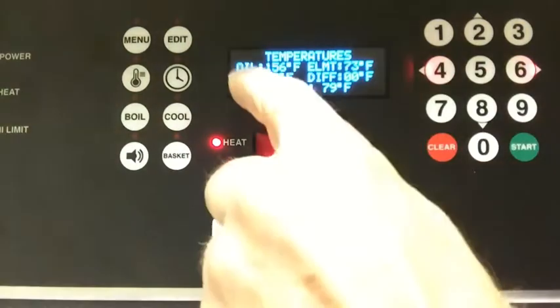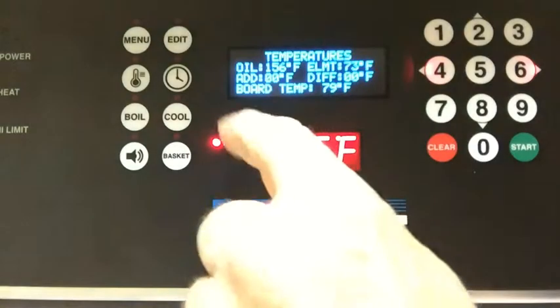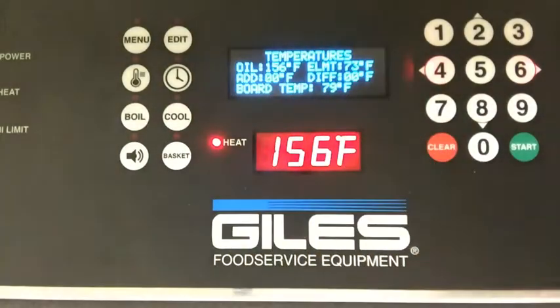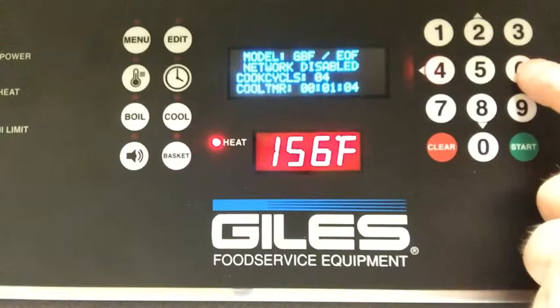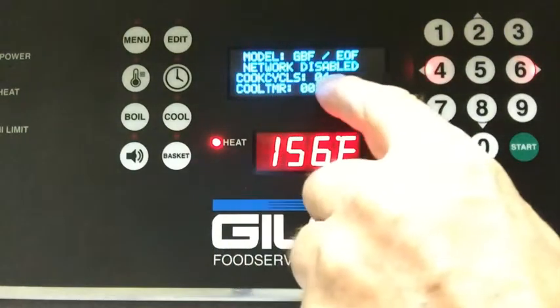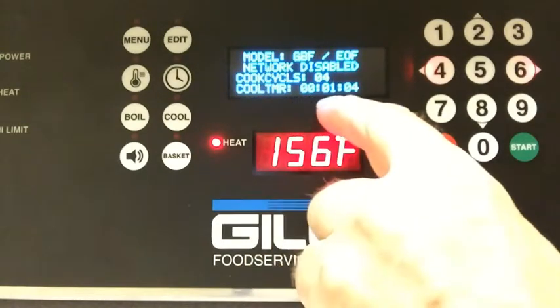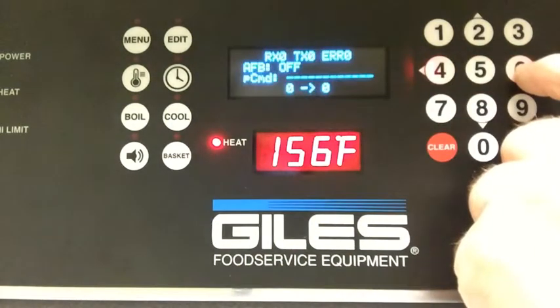You can see my element sensor. The add level you do not have on this machine, so you don't have the differential, but the board temperature is 79 degrees. So it allows you to look at those temperatures and see what's going on. You can go ahead and press the 6. It'll tell you what machine you've got, how many cook cycles have been run on this machine, how long the cook timers have been on.